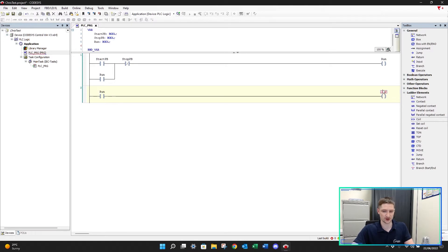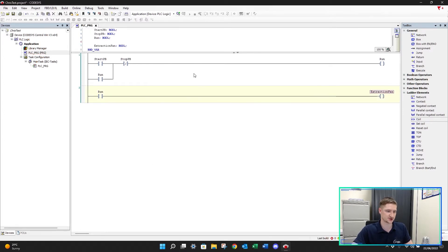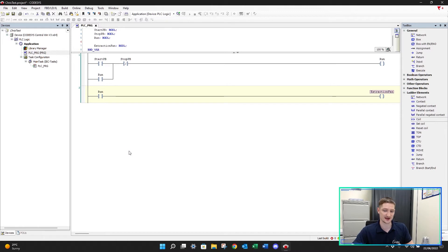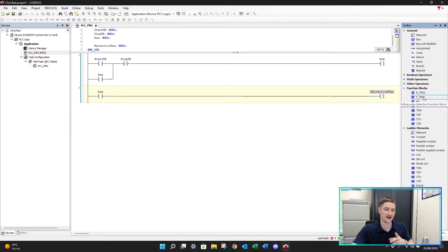I want to run an extraction fan - so there's my extraction fan. When we are running, the extraction fan is running. Now, in PLCs we have what we call rising triggers and falling triggers, and inside CodeSys they have the same. They have R_TRIG and F_TRIG, which detect the rising edge or the falling edge of the input. In this case I'm interested in the falling edge, because that's when the run signal turns off.